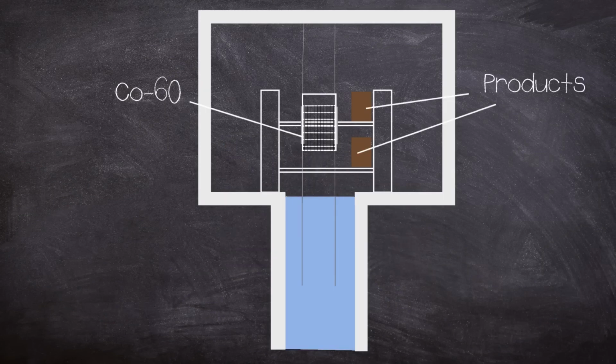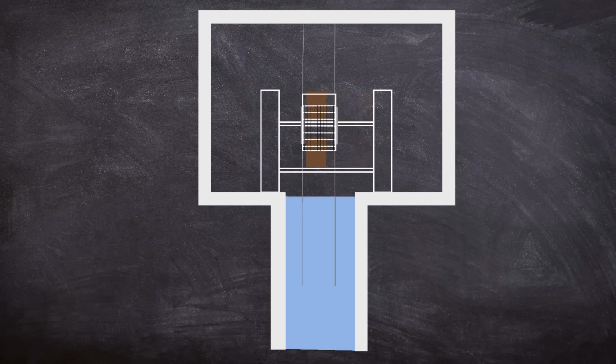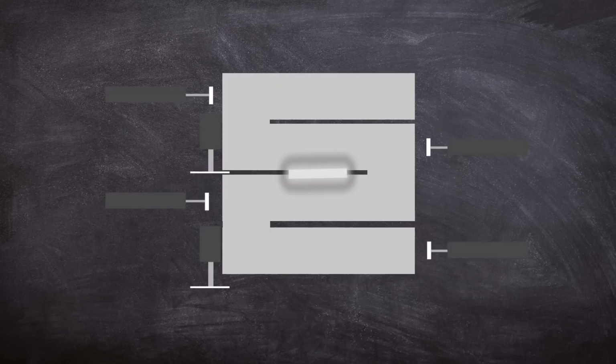Materials to be irradiated are usually placed in cardboard or fiberglass boxes. These containers are then themselves placed on a metal tray. Pneumatic pistons push the boxes along a set path over 2 levels, each time exposing a side of the box to the source. The path the boxes take results in 29 irradiation positions, and the time in each position was around 2 hours and 20 minutes.